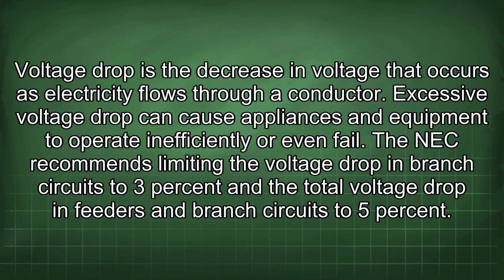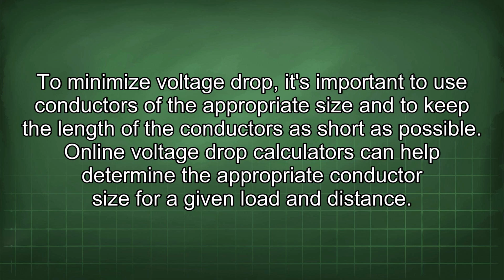The NEC recommends limiting the voltage drop in branch circuits to 3% and the total voltage drop in feeders and branch circuits to 5%. To minimize voltage drop, it's important to use conductors of the appropriate size and to keep the length of the conductors as short as possible. Online voltage drop calculators can help determine the appropriate conductor size for a given load and distance.